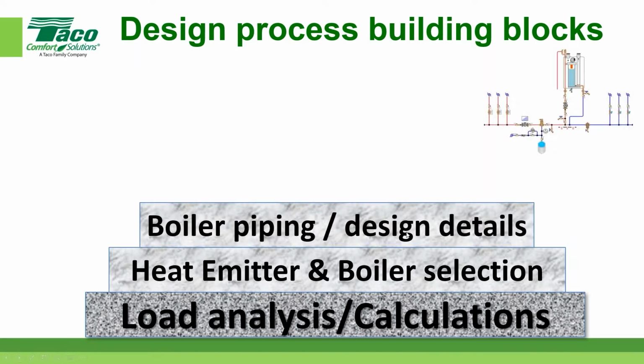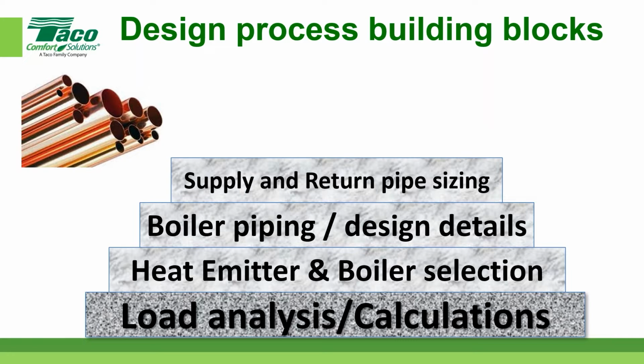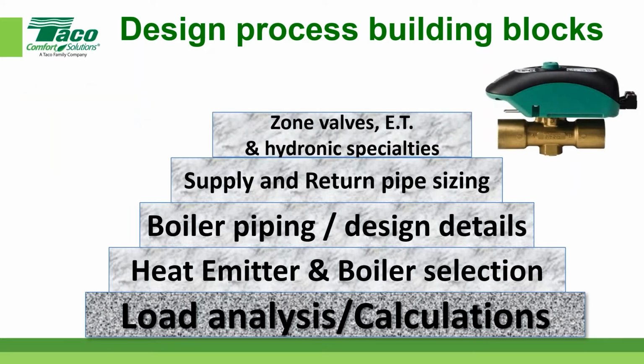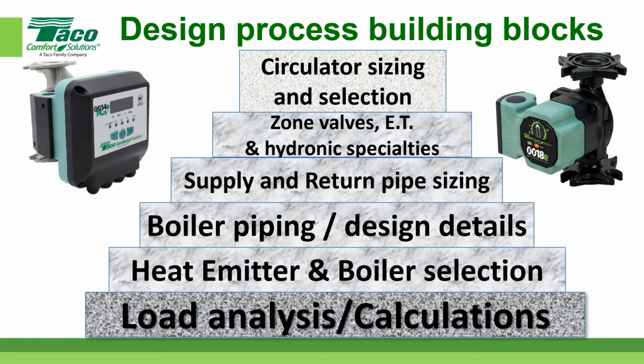Once we figure out what type of equipment we have, then we can look at the near boiler piping details and the things in and around there that will make sense. Then we look at supply and return piping, both for the boiler as well as the supply and return out to, let's say, manifolds, or a series out to baseboard runs or something along those lines. Then we've got all the hydronic specialty stuff like expansion tanks and zone valves and air separators and all the stuff that goes in and around the heating equipment. But last on this little pyramid, of course, is the circulator. In order to size the circulator correctly, we need to know all this stuff. Now, we're not going to cover everything today, but I've shortened it up to a point where you can see how this process would take. This is the slide I used to start a full day training course.